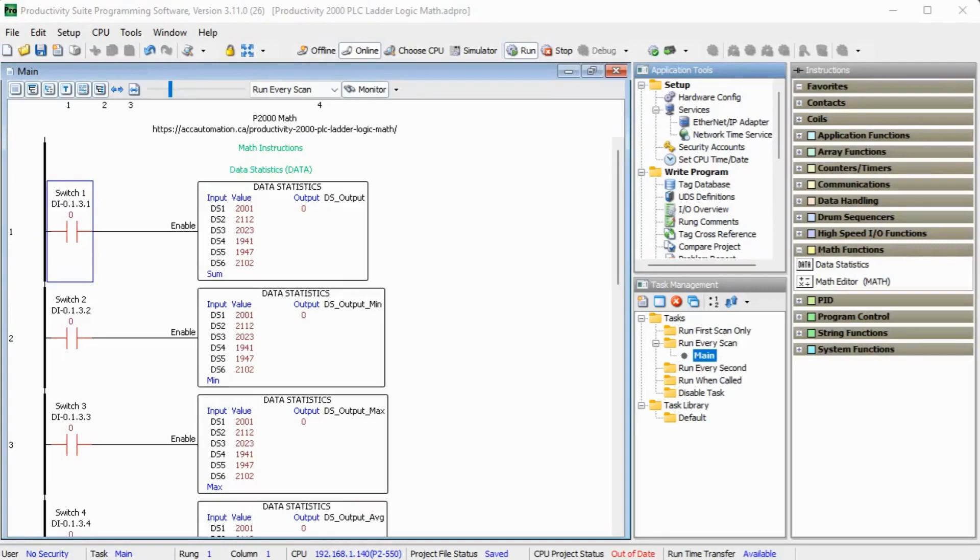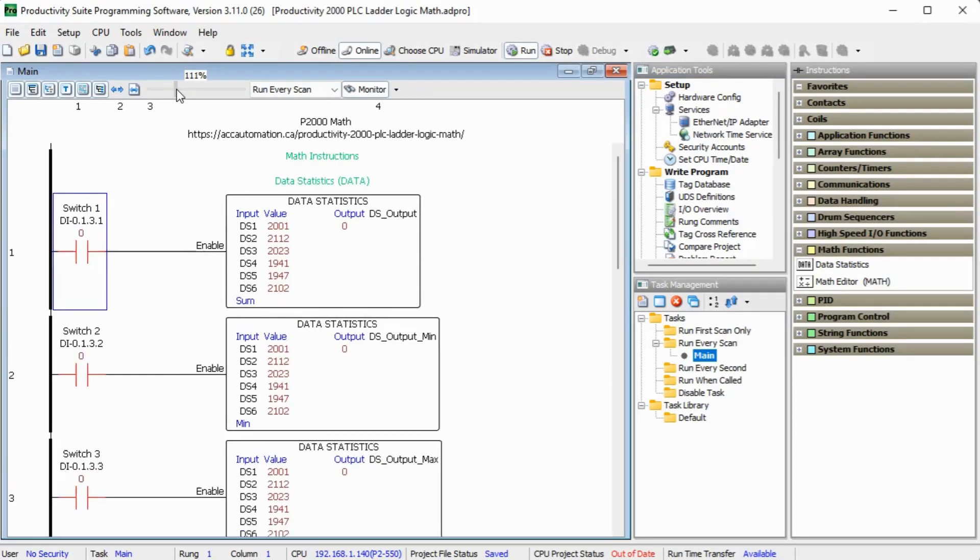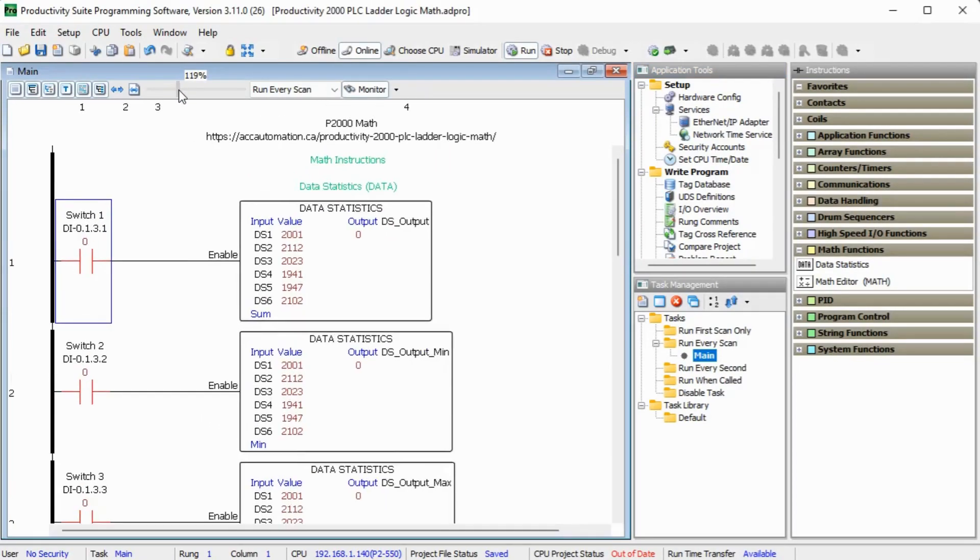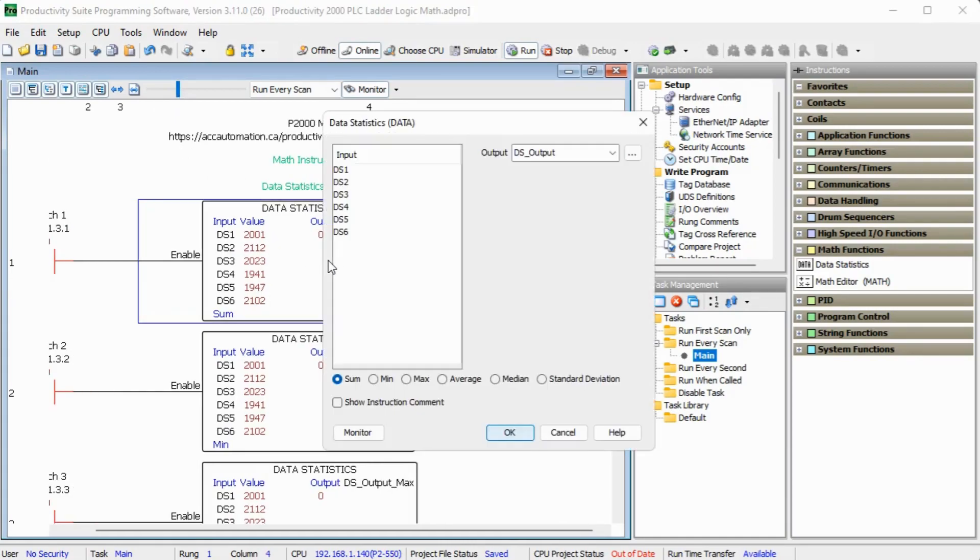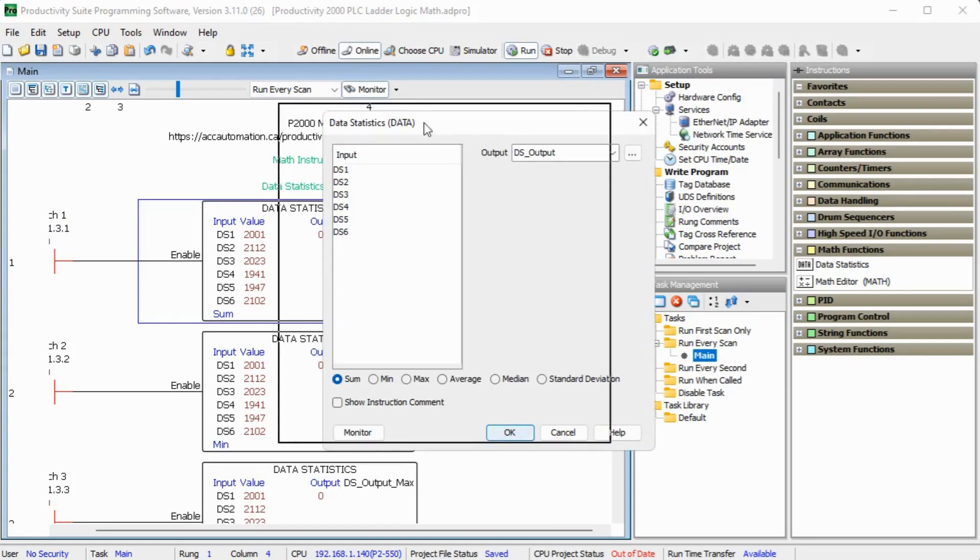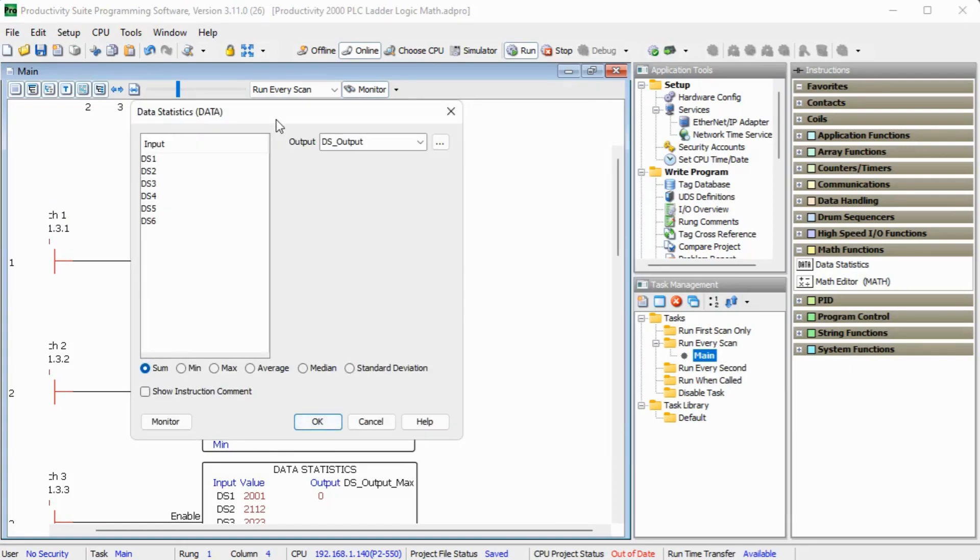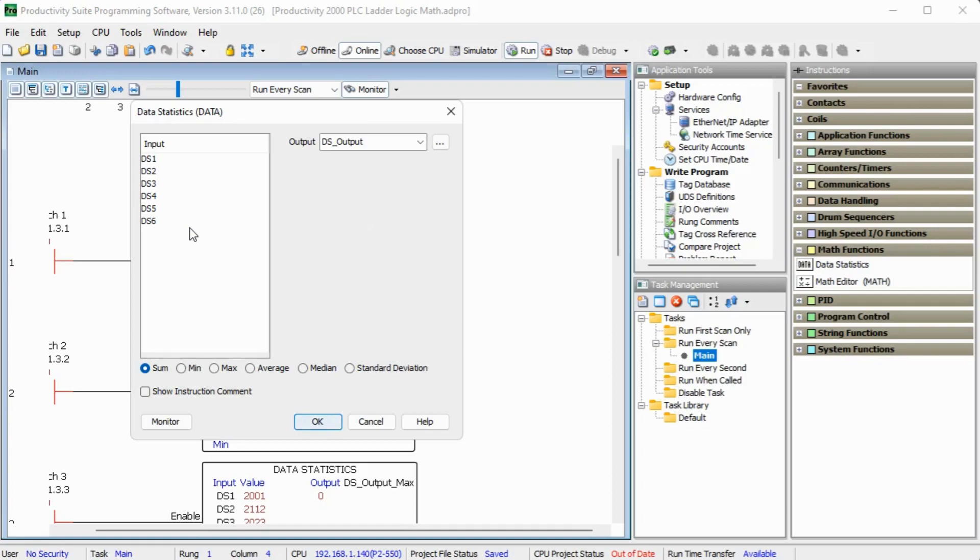The data instruction is used to find a mathematical statistic for up to 16 tags or constants. We can select one of the following: sum, min, max, average, median, or standard deviation. The instruction has an input and output section. This is where we input our tags. A radio button selection is at the bottom of the instruction to select what operation you would like to use.